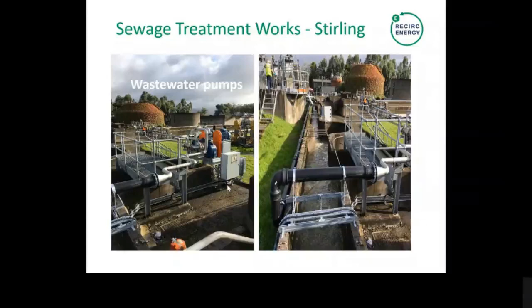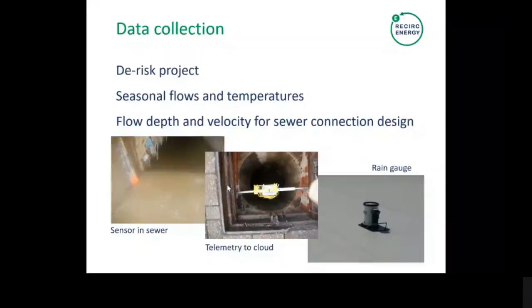One important aspect worth raising for these projects is it's really important to get proper data before embarking on one to de-risk it. Wastewater flows are seasonal; flows and temperatures change during the year. It's important to understand flow depths and velocities for sewer connection designs, and ideally, like on the Worthing project mentioned earlier, we'd collect up to a year's worth of data to understand what happens in spring, summer, autumn and winter in terms of flows and temperatures, and make sure the system is designed correctly. We can do high-level assessments before installing monitoring equipment, speaking to water companies to get model data, but we find that can be a bit variable in reliability.